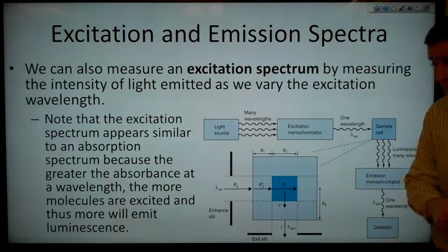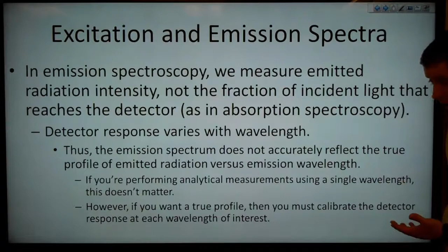So in emission spectroscopy, we measure the emitted radiation intensity, not the fraction of incident light that reaches the detector, as in absorption spectroscopy. So the detector response varies with wavelength, and that means that the emission spectrum does not accurately reflect the true profile of emitted radiation versus emission wavelength, because a detector isn't responding to different wavelengths with the same efficiency. So if you're performing analytical measurements using a single wavelength, this doesn't really matter. But if you want a true profile, then you must calibrate your detector response at each wavelength of interest.